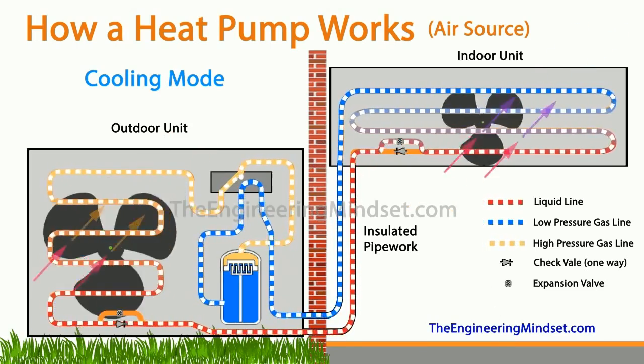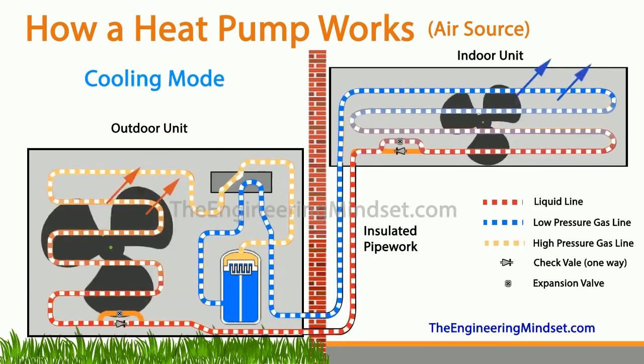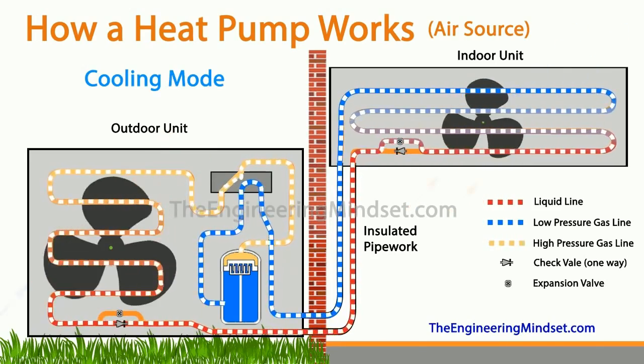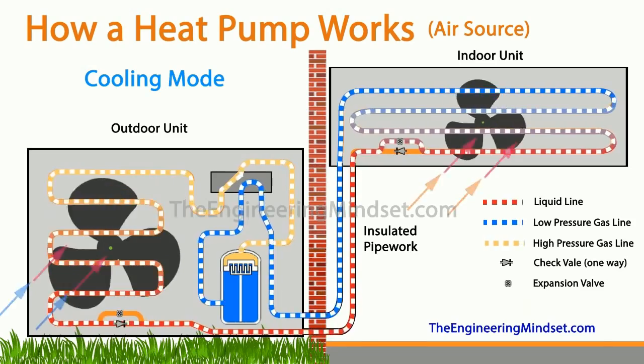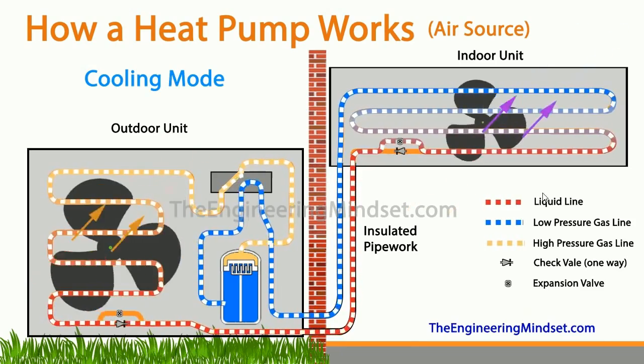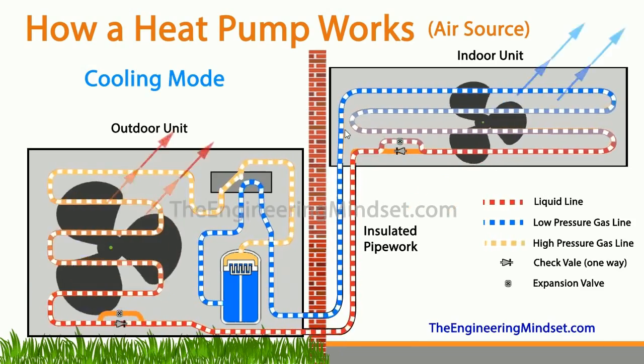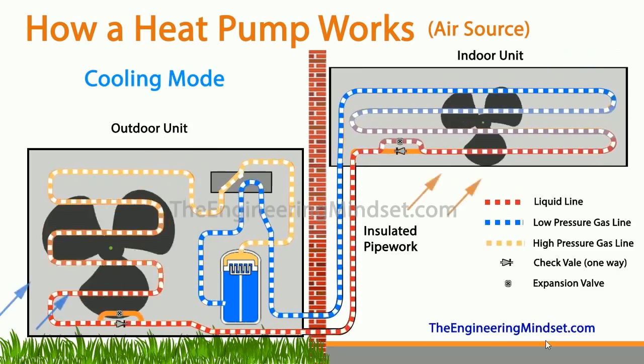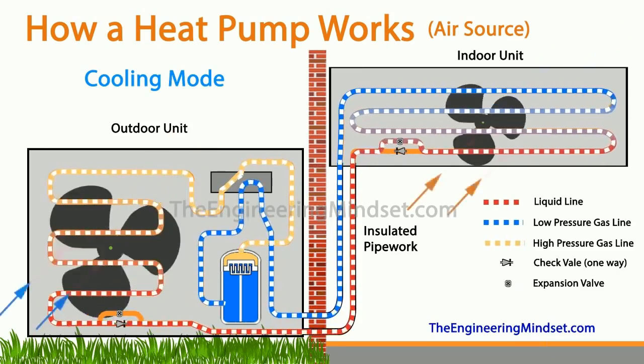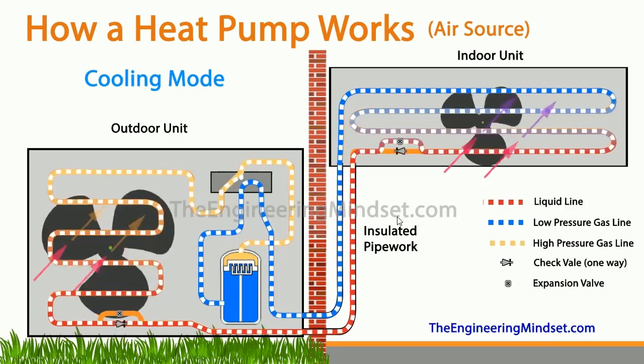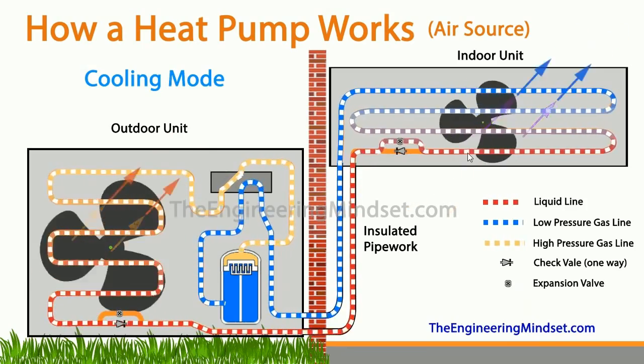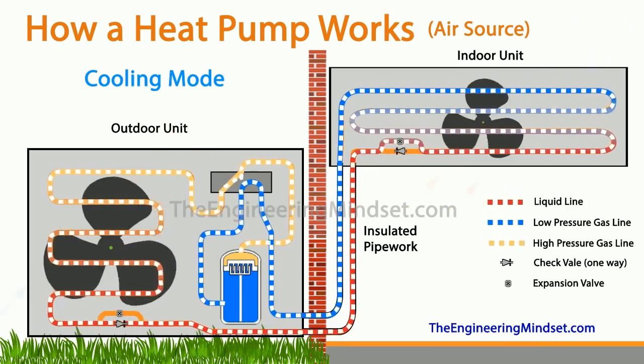The expansion valve obviously expands the refrigerant, so when it leaves the expansion valve, it will be a low pressure, low temperature liquid vapor mixture, and this will be pushed around this heat exchanger, and that will begin to pick up some of the thermal energy from the air that's being forced across the coil by this fan.